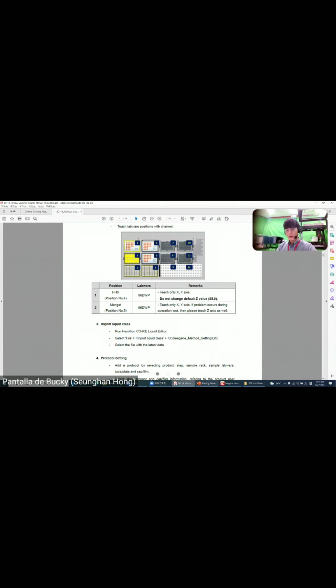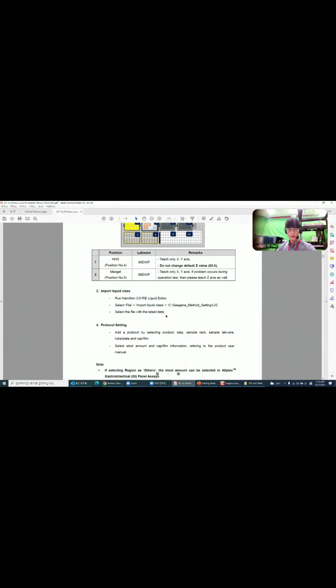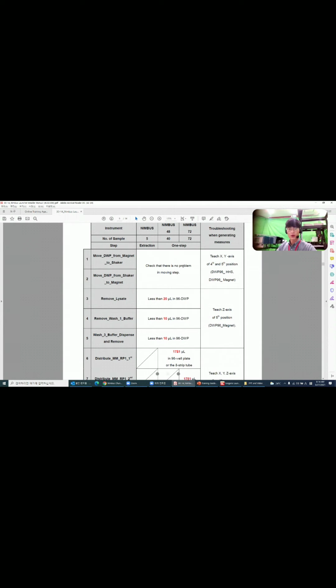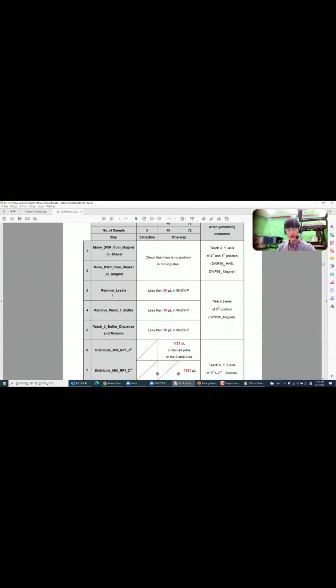The purpose of the water run is to check if the machine is working correctly, and we need to check some volume to see if the teaching is done correctly based on this table. Usually we're gonna select the one step RP for the water run. We're gonna use the water, except the beads. And right after the remove lysis, we have to measure the deep well plate, each well. The volume of each well has to be less than 20 microliter. And then do it again after remove the wash buffer 1 and 3.